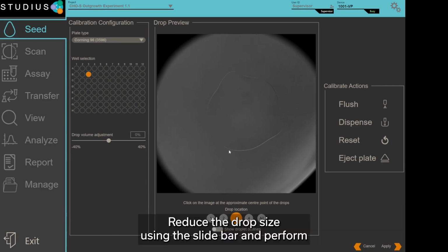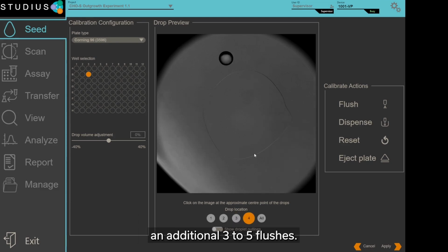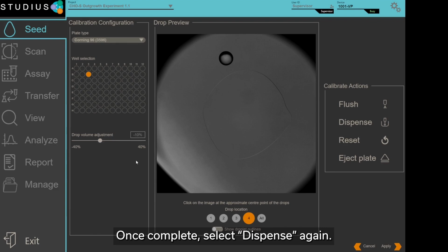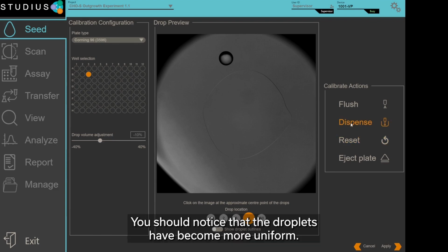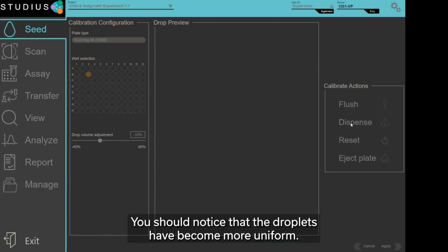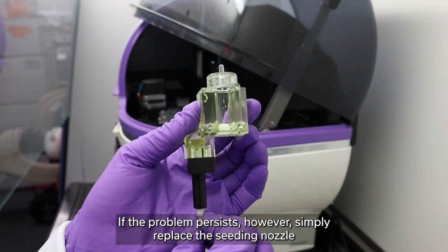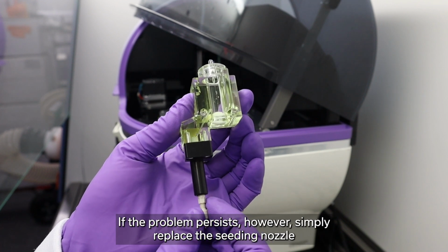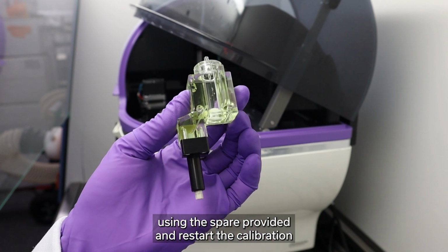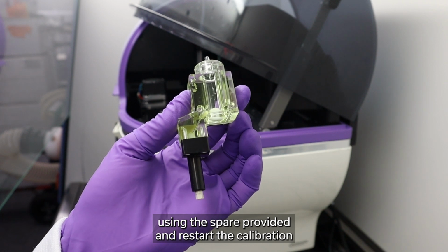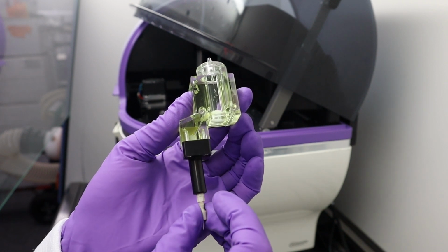Reduce the drop size using the slide bar and perform an additional 3 to 5 flushes. Once complete, select Dispense again. You should notice that the droplets have become more uniform. If the problem persists, however, simply replace the seeding nozzle using the spare provided and restart the calibration process.